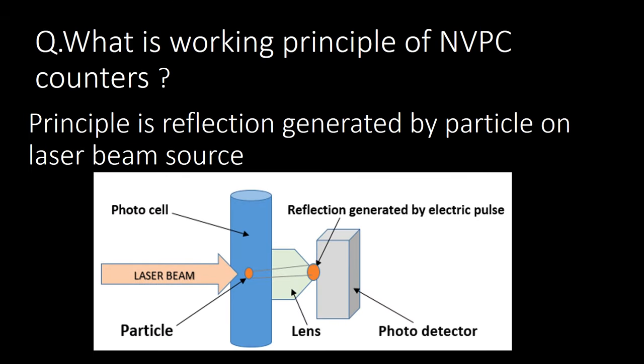What is the working principle of NVPC counters, or non-viable particle counting systems? The principle is based on the reflection generated by a particle on a laser beam source. These instruments are commonly used in the pharmaceutical industry. They contain a photocell; when a particle enters the path of the laser beam, it creates a reflection that generates an electrical pulse detected by a photodetector.